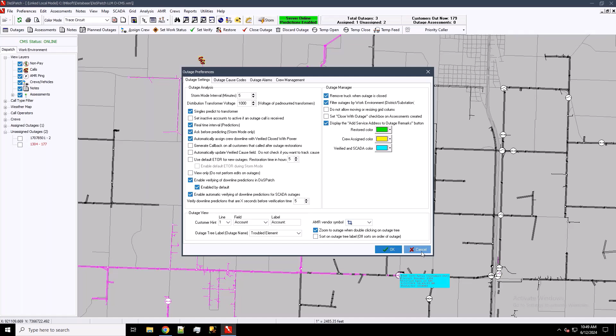And we can even set a time here in seconds for how long before the verification time that outage needs to have existed in order for us to verify it. So if they came in really close together, depending on that setting, we might roll them into one. But based on our settings here, this outage was definitely there 5 seconds before the SCADA operation came in. So we verified the existing fuse outage, locked it into place, and then verified open the breaker, taking out the other 177 customers. So now we might send a crew out to work this outage.